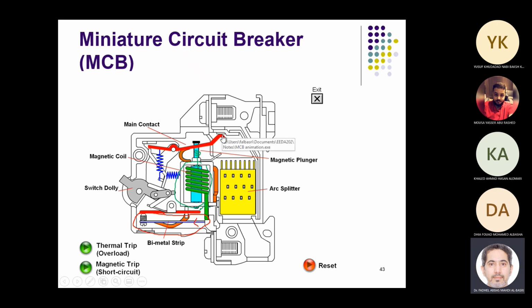So we have here two contacts. This is the moving contact, the blue one, and the fixed contact is here. One wire comes through this screw, and the circuit continuity goes from this to the coil, then to the thermal element, then from the thermal element to the second terminal. And we have a mechanism, an arc splitter. When you try to open these contacts, an arc is initiated, and especially during a short circuit the arc is larger, and to keep this arc from exploding the breaker, you need to split it to reduce its energy until it is extinguished.